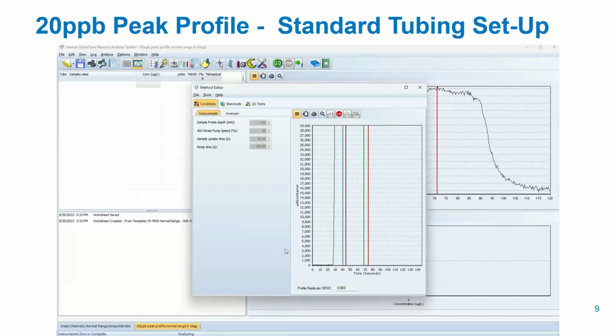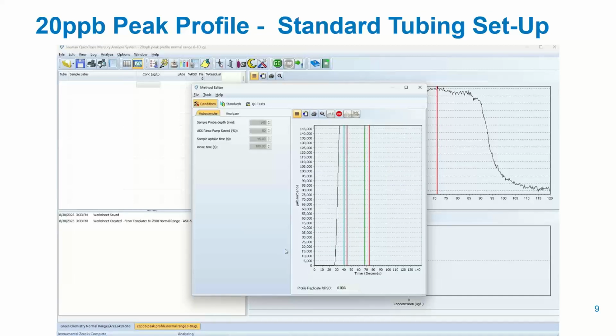So as I mentioned before, this is from a template, so the baseline and the integration time will need to be adjusted to meet our needs. So you can see the baseline is going to be in the middle of the peak right now. So we're going to have to adjust that to a flat part before the peak starts to rise. And for the integration time, it should be across the flattest part of the plateau. So not too close to what I call the shoulder or the front side of the peak, and not too close to the dip from the air slug moving through the gas liquid separator.